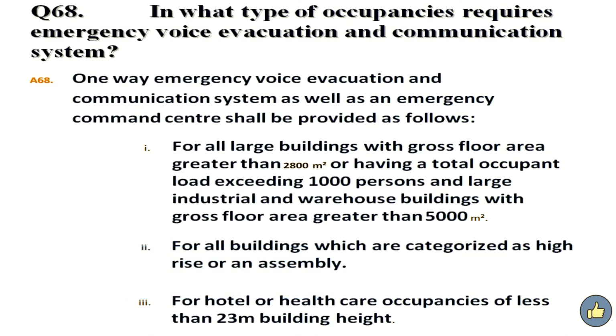In what type of occupancies is an emergency voice evacuation and communication system required? Answer. A one-way emergency voice evacuation and communication system as well as an emergency command center shall be provided as follows. Number 1. For all large buildings with gross floor area greater than 2,800 square meters or having a total occupant load exceeding 1,000 persons, and large industrial and warehouse buildings with gross floor area greater than 5,000 square meters. Number 2. For all buildings which are categorized as high-rise or assembly. Number 3. For hotel or healthcare occupancies of less than 23 meters building height.